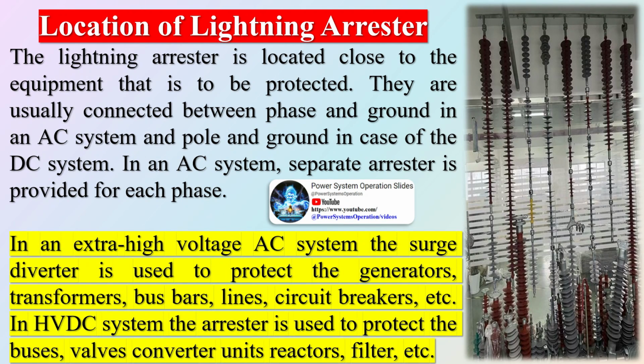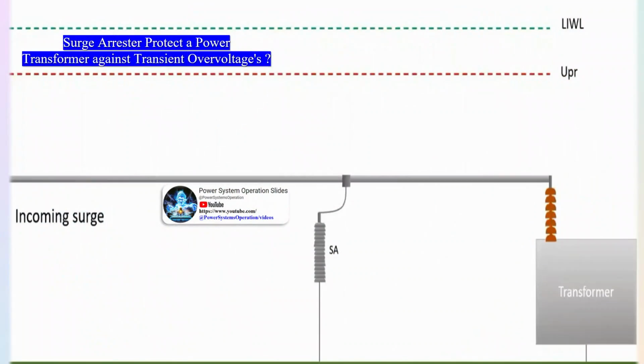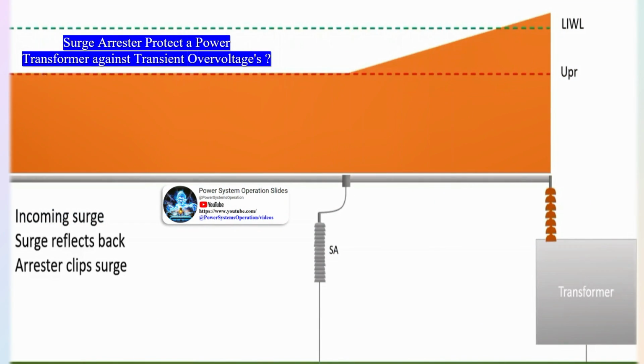Ground lead: the ground lead is a conductor that connects the surge arrestor to the grounding system of the power system. It provides a low impedance path to ground for the transient energy, diverting it away from the protected equipment. There are several types of surge arrestor commonly used in power distribution networks. These include station-class surge arrestors. These are large surge arrestors designed for use in substations and other high-voltage applications.